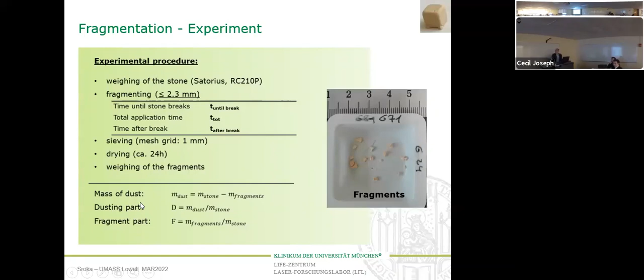When we calculate the weight of the fragments, and we know the stone mass before, we make a subtraction, and then we get something like dust, which we cannot really catch in this water area. So we sieve it with meshes and so on, and dry it, under the same conditions as before. We measure the time when the stone first breaks, then the total application time, and when we make a subtraction, we have the time after break as well. From the mass we do the same as I already told you. So with this we can see different conditions. These are the laser parameters: 1 joule and 10 hertz, 0.5 joule and 10 hertz, and different pulse durations.